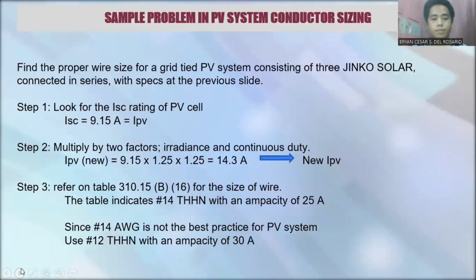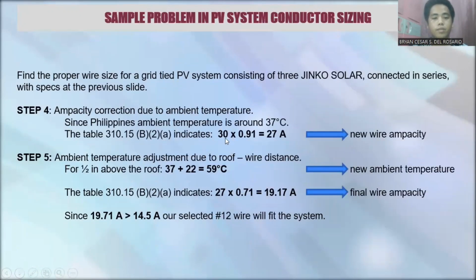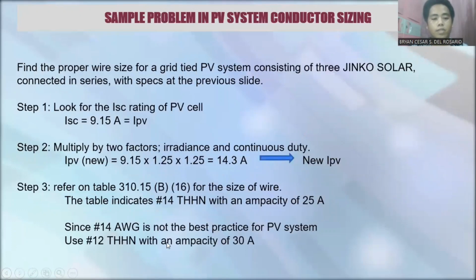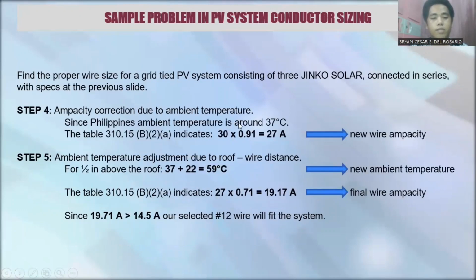The 30 amperes we got from the 12 THHN wire with ampacity of 30 ampere, we multiply by 0.91 from the table. This gives us a new wire ampacity of 27 ampere.